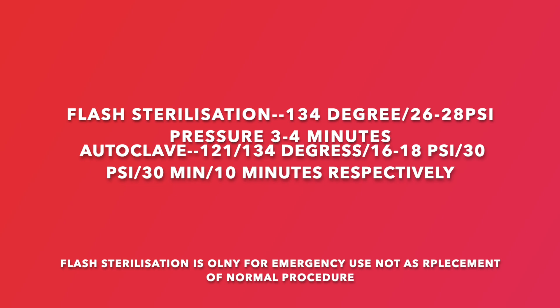So usually it takes 30 minutes and 10 minutes, depending upon the temperature we are using. At 121 degrees Celsius it will take 30 minutes, and at 134 degrees Celsius it will take 10 minutes. The whole procedure is that we clean the instruments, wrap the instruments in the trays, in two towels, and then place the instruments in the autoclave. So it takes the time. This 30 minutes is basically the time that is given to the process at the desired temperature of 121 degrees Celsius and 16 to 18 psi of pressure.